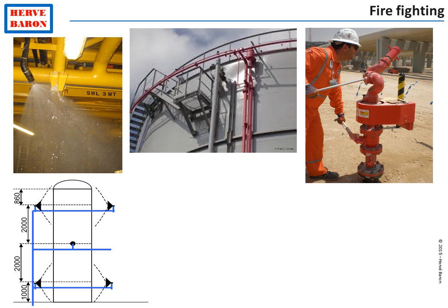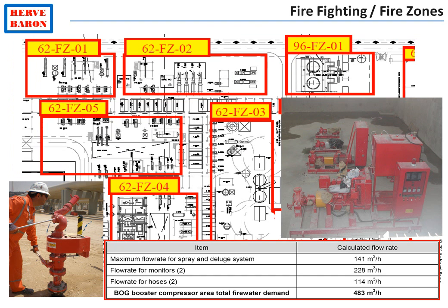Spraying water on equipment can be done automatically by what is called a deluge system, or can be done manually by a fire monitor. A deluge system is provided systematically on all equipment of offshore facilities due to their close proximity. It is scarcely used onshore as access is available to spray equipment manually with fire monitors. Once the plant territory has been split into different fire zones, safety estimates the amount of fire water required for firefighting in each fire zone, and then takes the maximum amount among all fire zones to define the capacity of the fire water storage and pumping system.